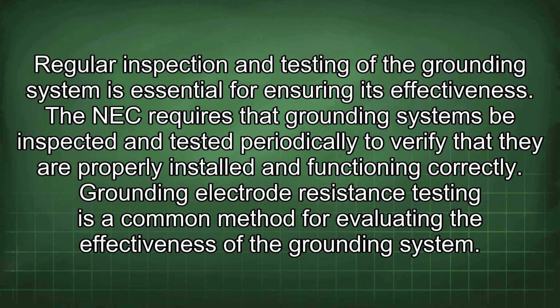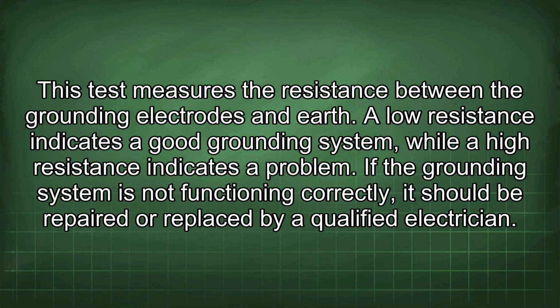correctly. Grounding electrode resistance testing is a common method for evaluating the effectiveness of the grounding system. This test measures the resistance between the grounding electrodes and earth. A low resistance indicates a good grounding system, while a high resistance indicates a problem. If the grounding system is not functioning correctly, it should be repaired or replaced by a qualified electrician.